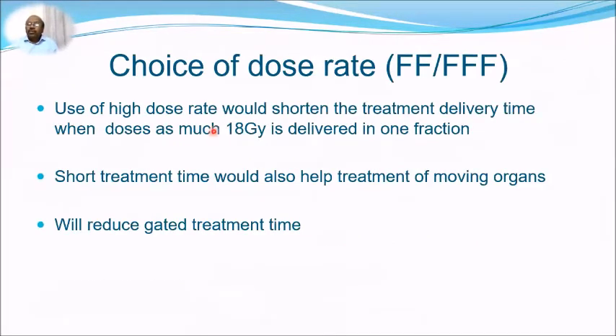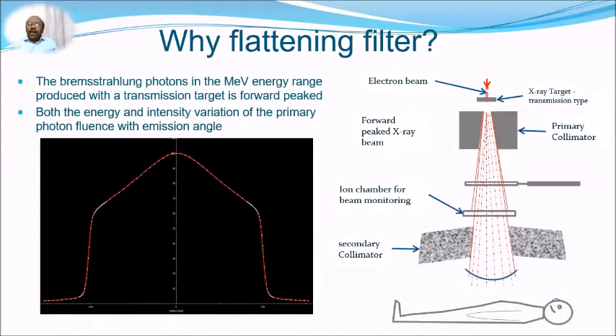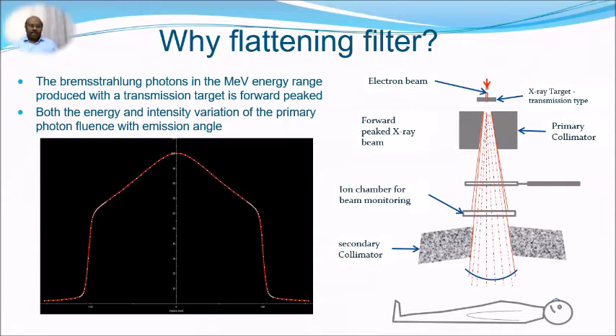Use of high dose rate shortens treatment delivery, which is important when delivering very high single-fraction doses such as 18 Gy, and also reduces gated treatment time. Regarding flattening filter-free (FFF) beams: the bremsstrahlung photons in the MV range produced at the transmission target are forward-peaked, resulting in a peaked beam profile without a flattening filter.